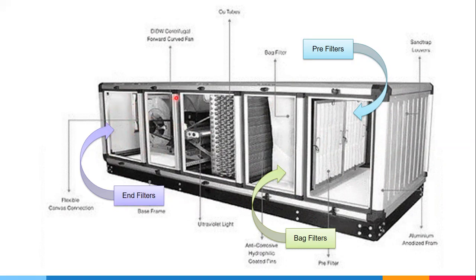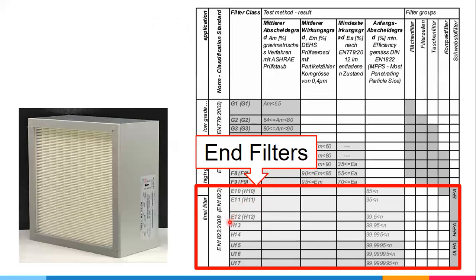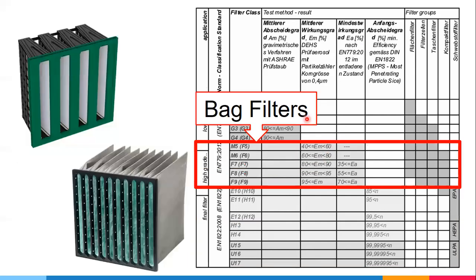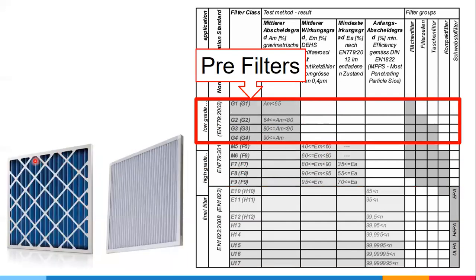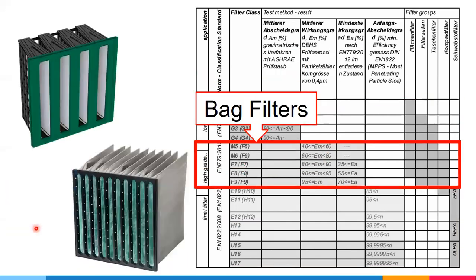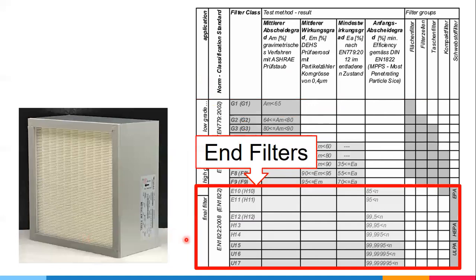Why after the fan? Because these filters have special functions. The first filters are the pre-filters, which take out the coarse particles. The second are the bag filters, which take out the finer or smaller particles. The end filters are the ones that comply with special requirements, like additional cleanliness, or sometimes chemical filters are also end filters.